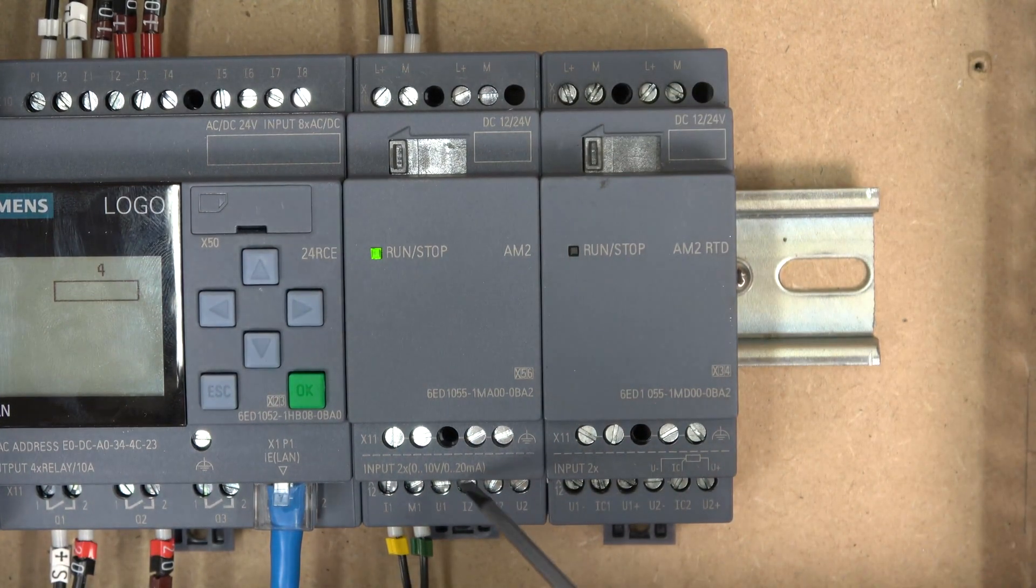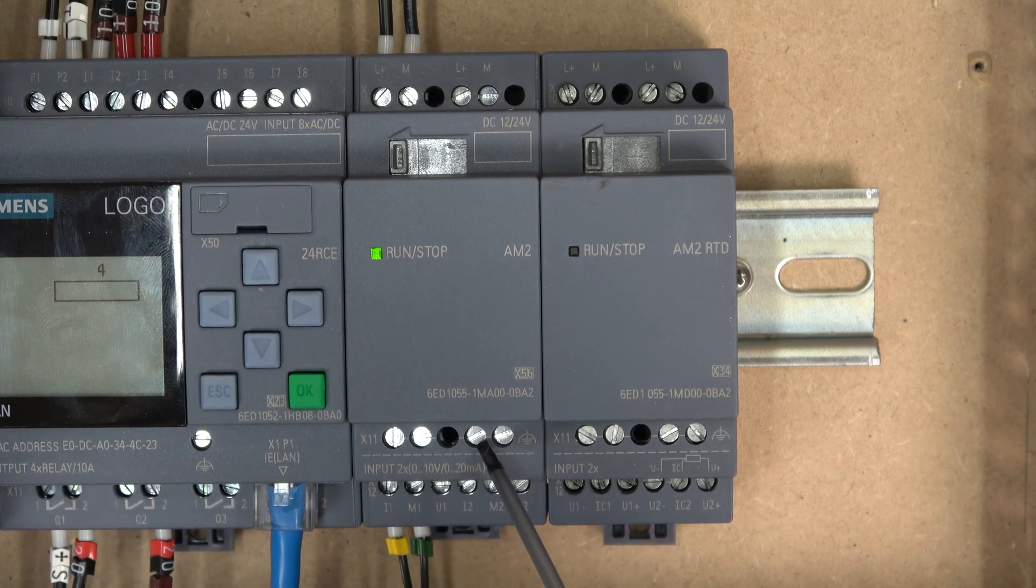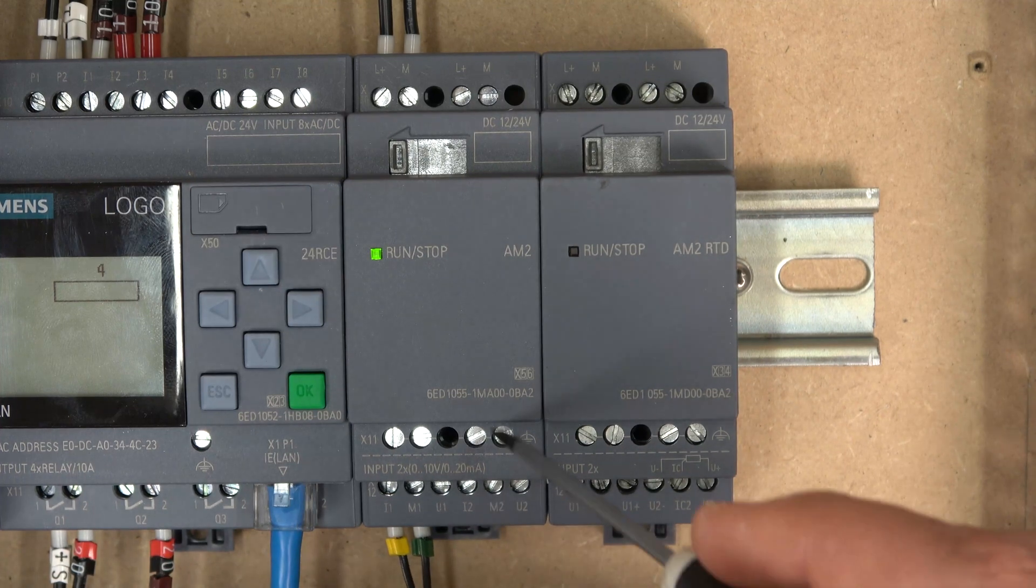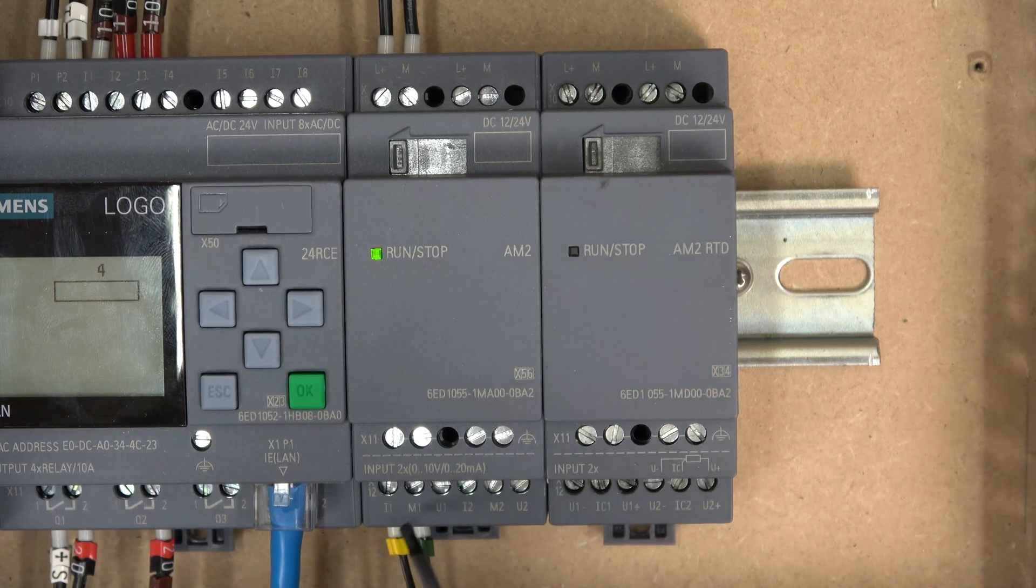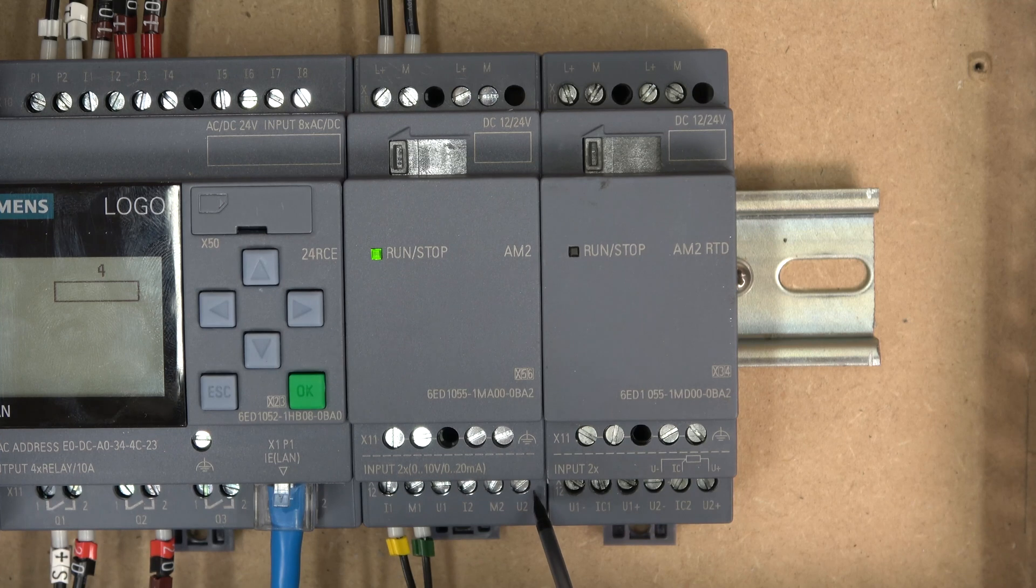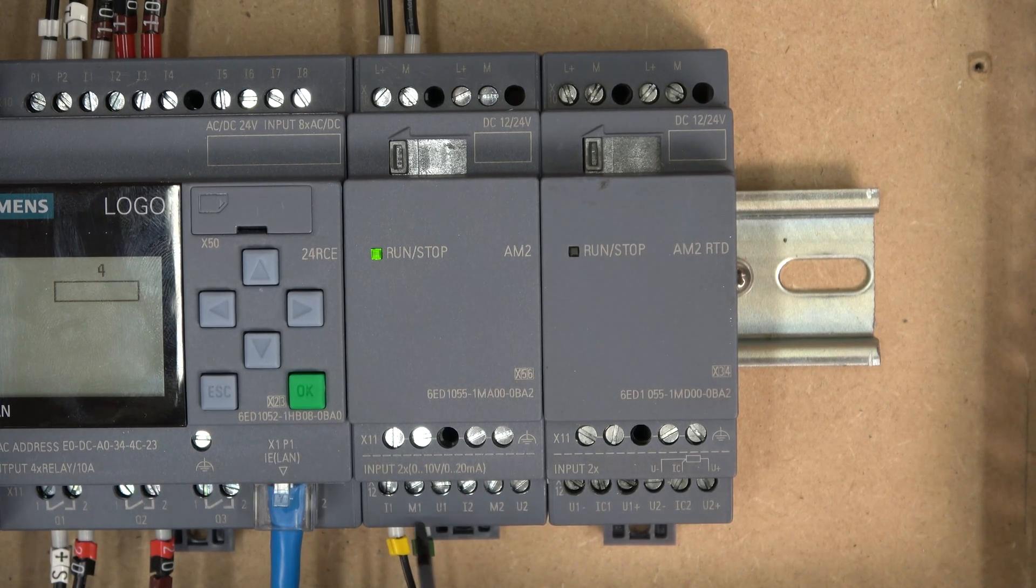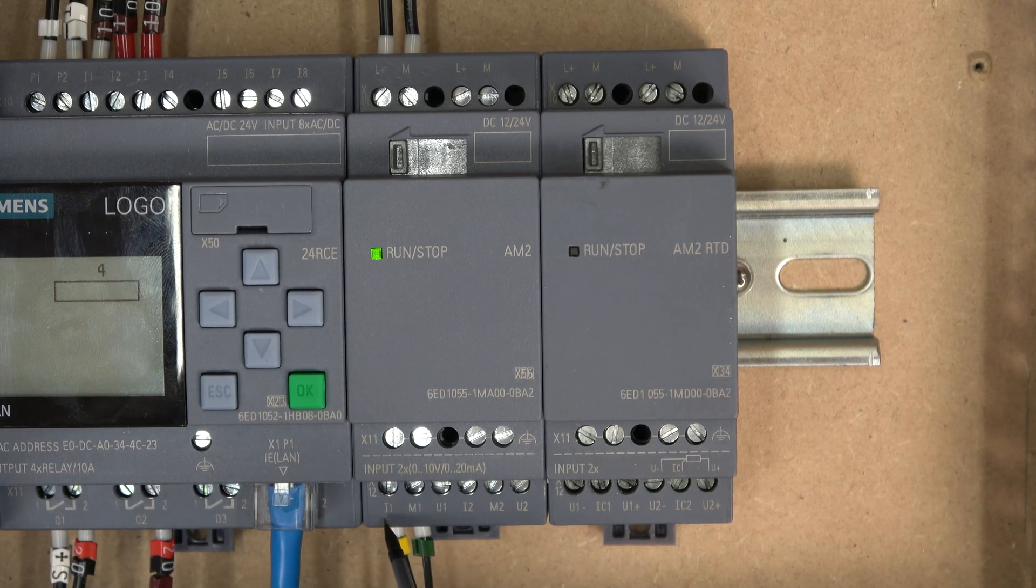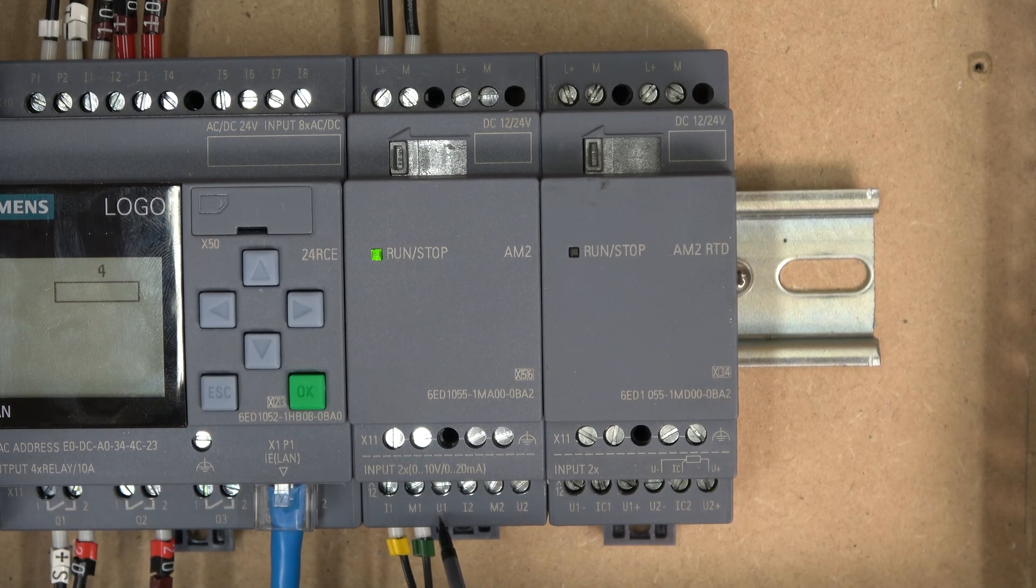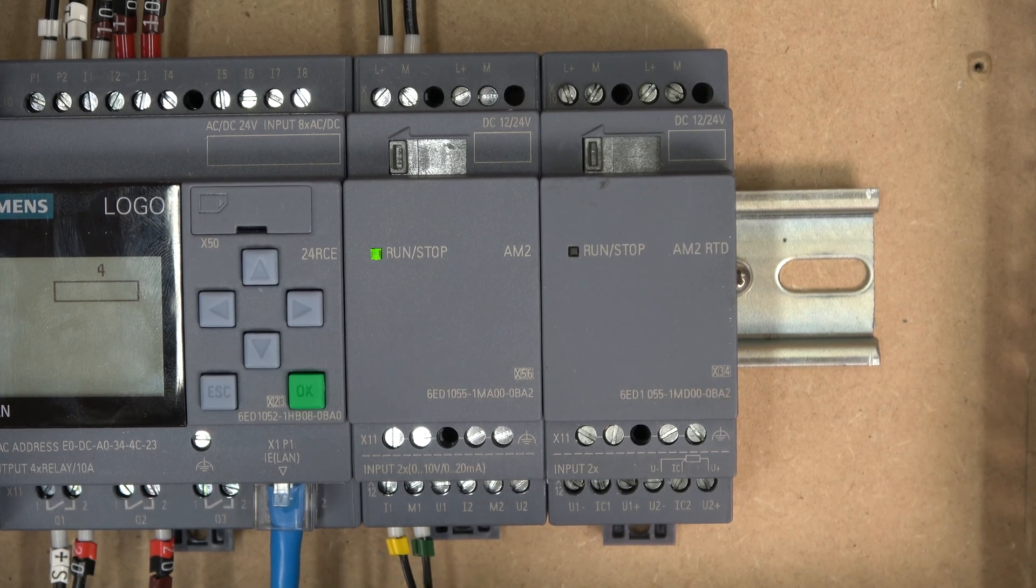So when it comes down to this side, these guys in here are for your shielding and earths. And when you come down here, this is where you would be pushing in your analog signals. So if you look in here, you can get I1, M1 and U1 or V1. So I stands for current and V or U stands for volts. And this M1 is your negative, pretty much.